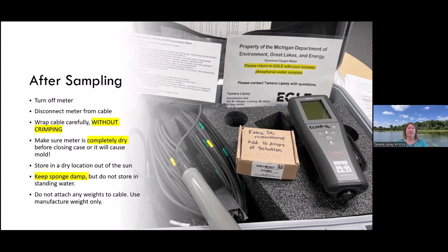This includes the cable, so that might take some time, or it will cause mold. I have had a couple, especially with these heavy duty cases, come back, and I open them in the fall, and they are full of mold because it was wet when it was put away. Store the meter in a dry location out of the sun. And when you're drying it out, same thing. Make sure you maybe have it in your garage and open so it can dry out.